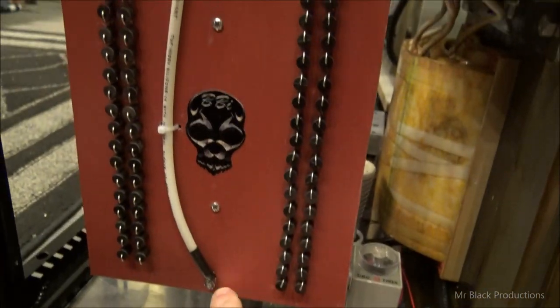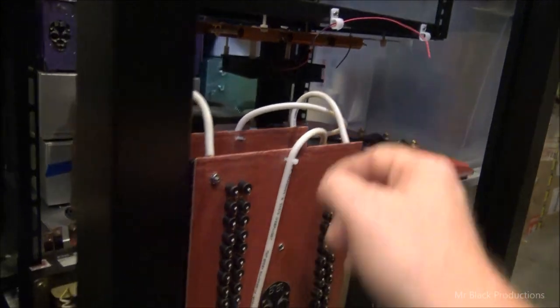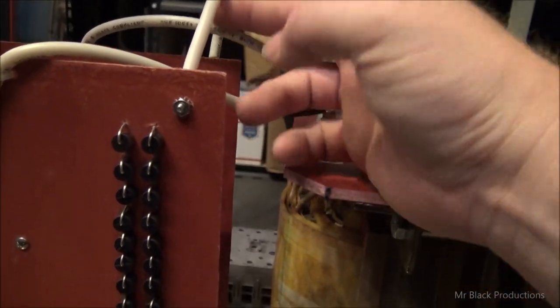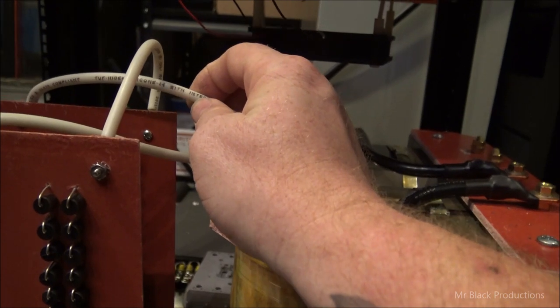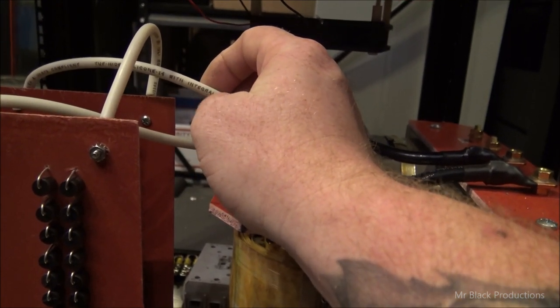And on this side, we've got our DC outs. Over here is our AC in. Same thing over here. And there's plenty of real estate. This is 1500 volt wire. So there's plenty of space around all of these wires, and they're not in contact with anything that might be possibly conductive. Even though in theory, you could lay this right down against the edge of the cabinet.